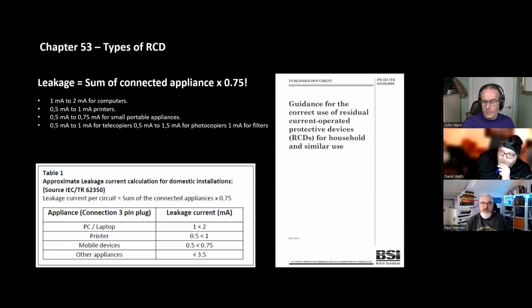So if I then show you, as a Brucey bonus, PD IEC Technical Reports, you don't have to buy it, it's here. This is all the relevant bits that electricians need to know. Really simple. It's about leakage of connected appliances. So leakage from a circuit can be worked out via the sum of connected appliances, i.e., let's say there's 10 PCs, and we use the worst case of leakage current. Let's say it's 2 milliamps. So it's effectively 10 times 2, 20 times 0.75. That's your design leakage of the installation.